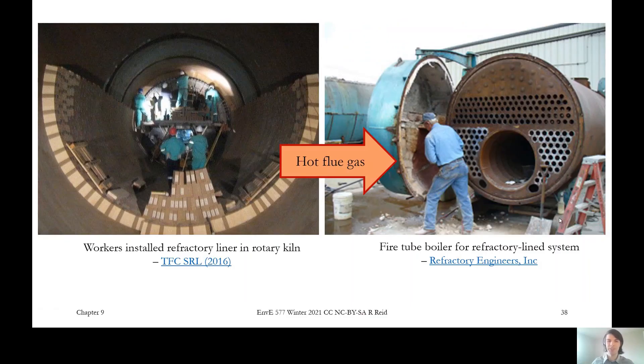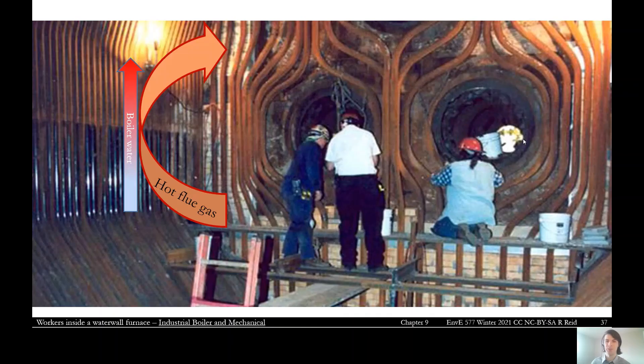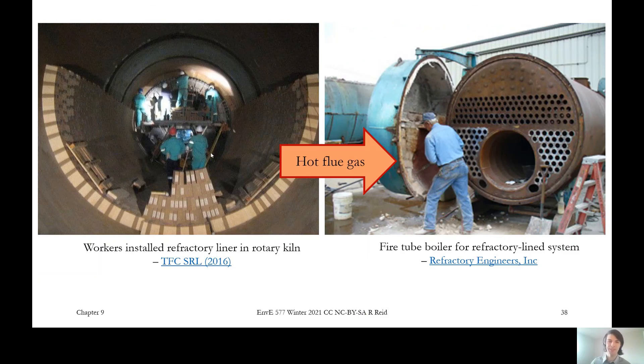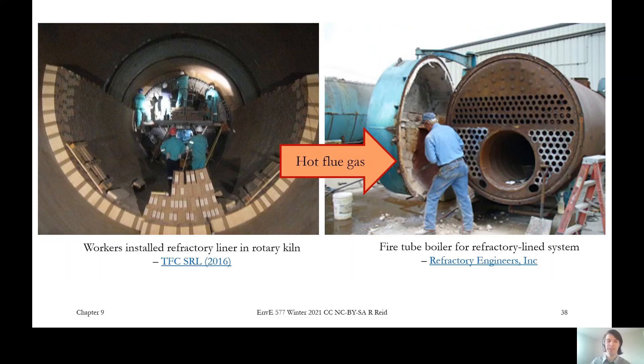In the refractory system, instead of pipes contacting hot gases in the reactor walls, the system is lined with refractory bricks. This is visible during maintenance on a rotary drum style incinerator. The actual boiler where heat is extracted from the flue gas is separate — all the energy comes out of the combustion chamber and goes into this external boiler, which has tubes doing the same job as those in the water wall, just in a separate unit. Most plants use the water wall system; the refractory system may be more suited to smaller mass burn plants.